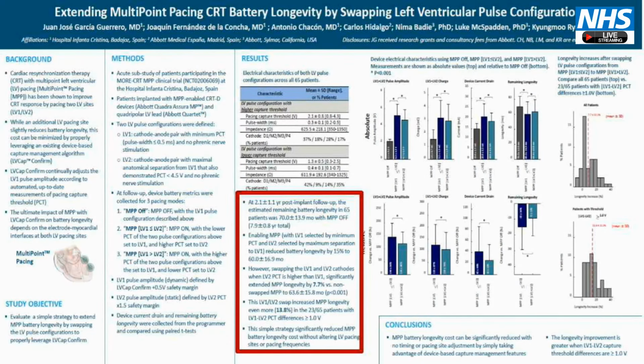In Abbott devices, with diligent programming of LV vectors, essentially which pole is paced first, and therefore has the automatic threshold management algorithm functional, we again see longevity reductions of about 6 months overall. In Mr. Ayub's case, we have seen a reduction in longevity on the programmer from out of box at 7.1 years, and with multi-point pacing turned on, 6.3 years.